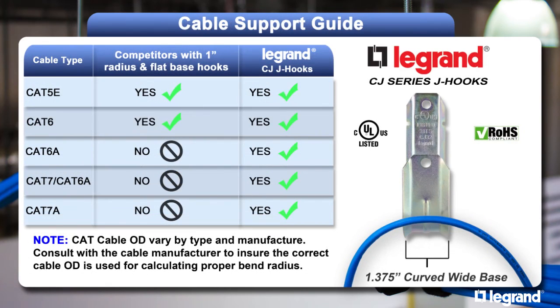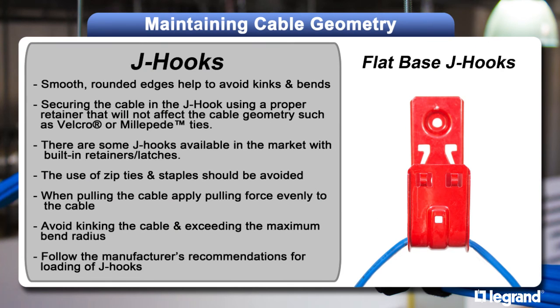A cable support with a 1-inch base creates a situation where the minimum bend radius could be exceeded. Cablofil's CJ Series J-hooks support a minimum bend radius of 1.375 inches, which is optimum for high speed cables such as CAT-7A. A cable support with a flat base tends to cause an abrupt bend as compared to a hook with a beveled or rounded base.